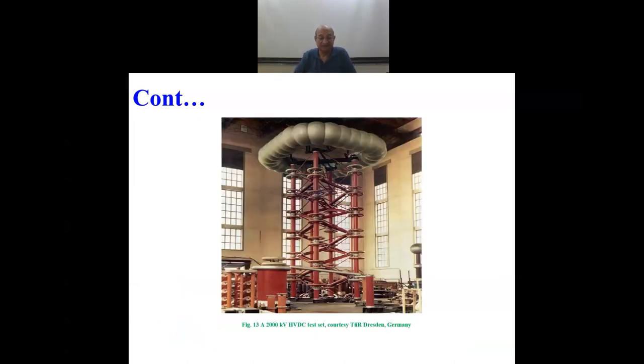This is a typical photograph. As you can see here, it is very high voltage. As I said, this is a 2000 kV high voltage DC test set, and these DC test sets have a very, very small current rating. This may be half an ampere or a maximum of 1 ampere of current, because, as I explained, when you apply DC to a capacitor, there is no charging current requirement. It is only the current required by the DC resistance offered by the dielectric, which is very, very high, to the tune of hundreds and thousands of megaohms. So the current requirement is very low.